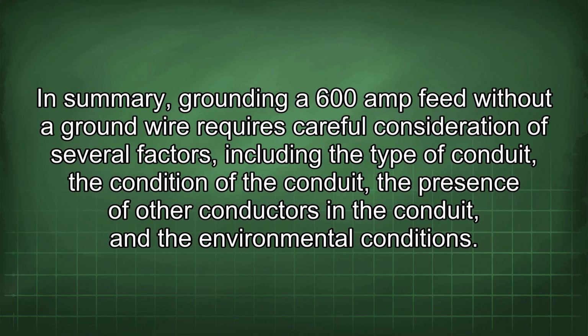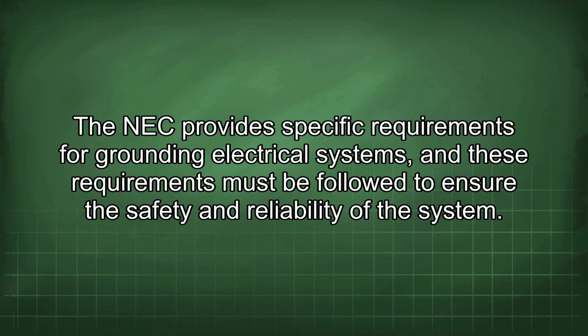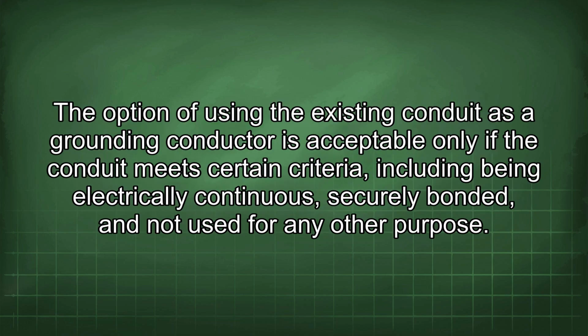In summary, grounding a 600 amp feed without a ground wire requires careful consideration of several factors, including the type of conduit, the condition of the conduit, the presence of other conductors in the conduit, and the environmental conditions. The NEC provides specific requirements for grounding electrical systems, and these requirements must be followed to ensure the safety and reliability of the system. The option of using the existing conduit as a grounding conductor is acceptable only if the conduit meets certain criteria, including being electrically continuous, securely bonded, and not used for any other purpose.